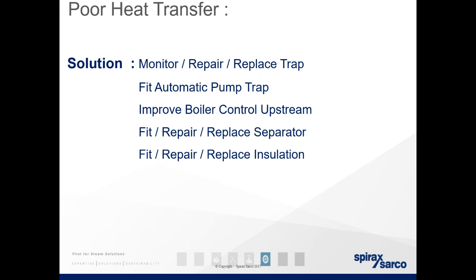If you have no ability to do that, then add an automatic pump unit. Improve boiler control upstream. Again, the better quality steam you produce and feed to your process, the better quality and heating times you will have. Fit, repair or replace separators. A separator is effectively a void space for you to enter steam in, and any particulates or water carried in that steam drop out by hitting the internal plate and dropping down to the steam trap. And fit, repair or replace insulation, so you see less atmospheric losses.